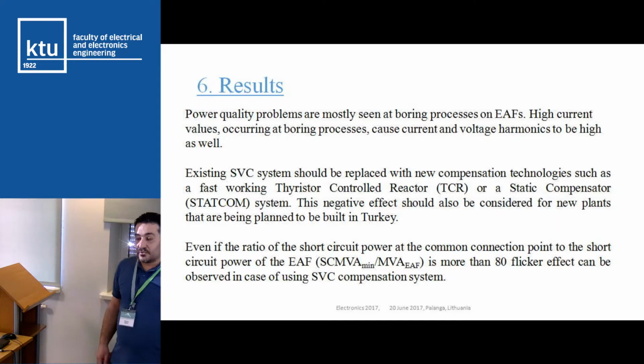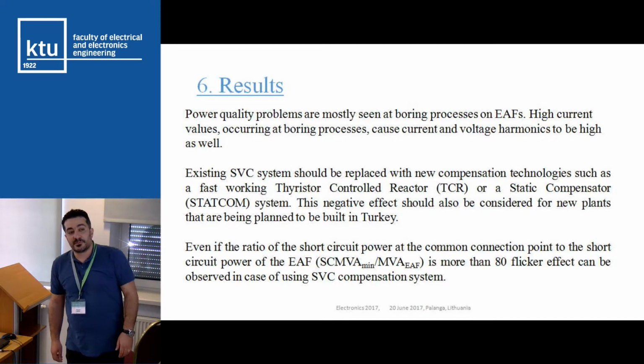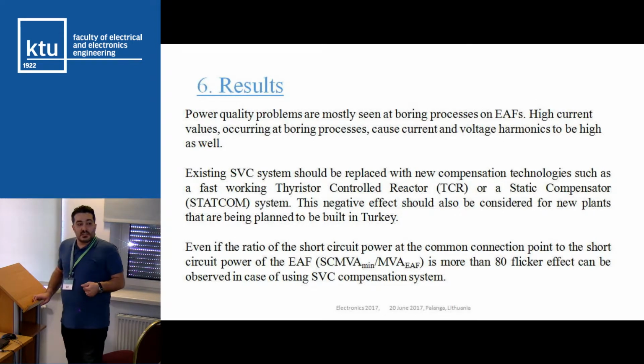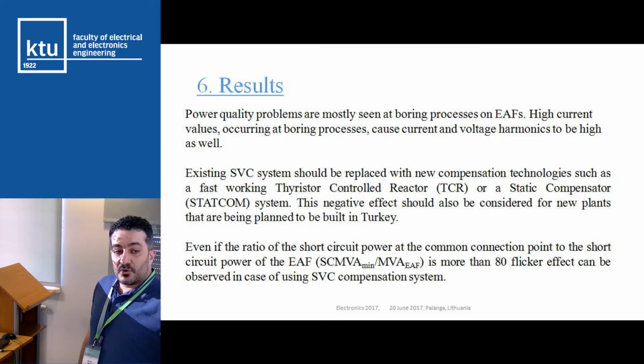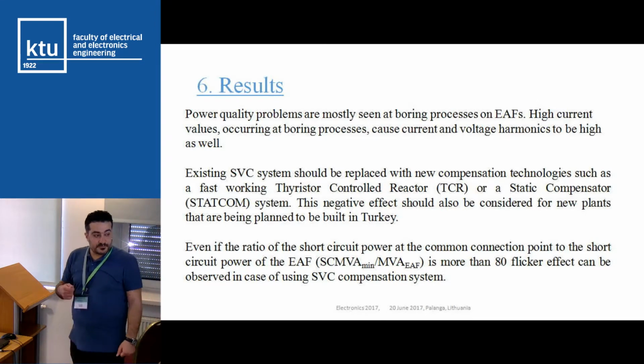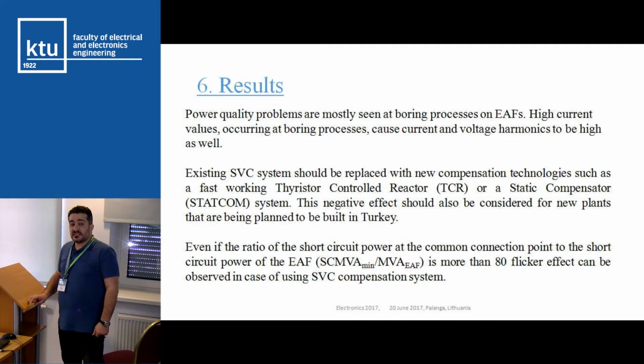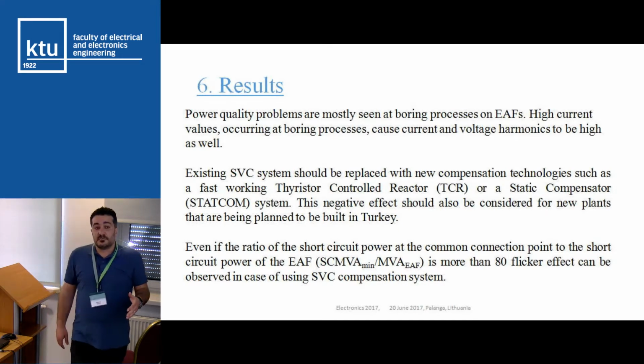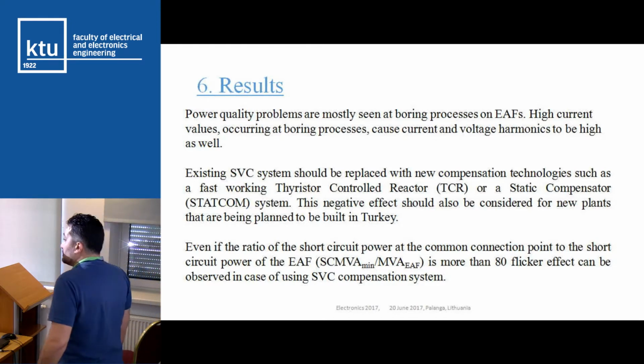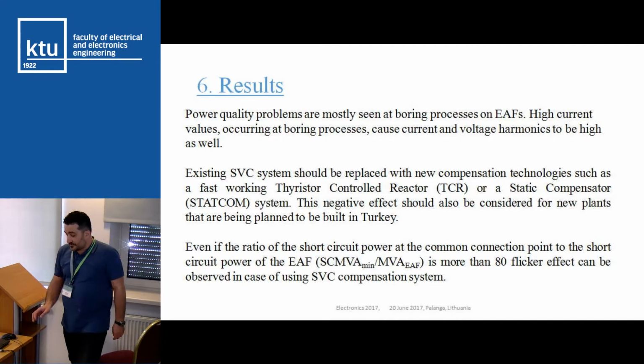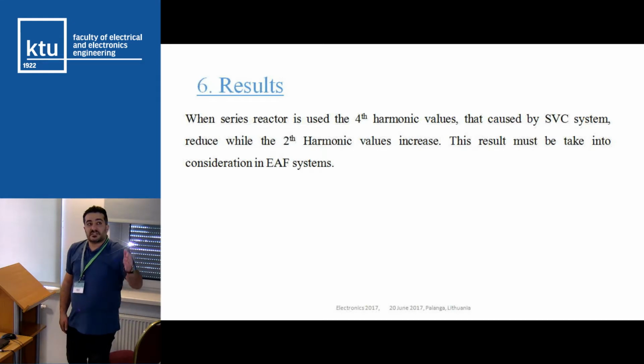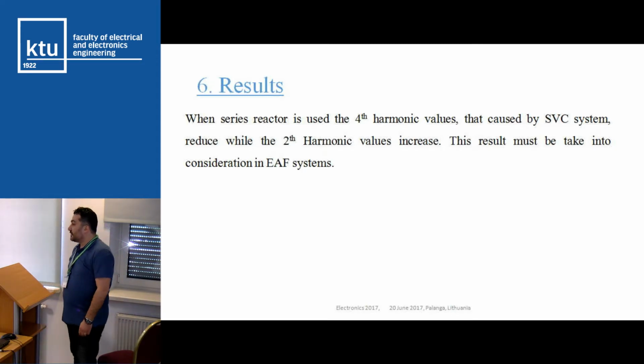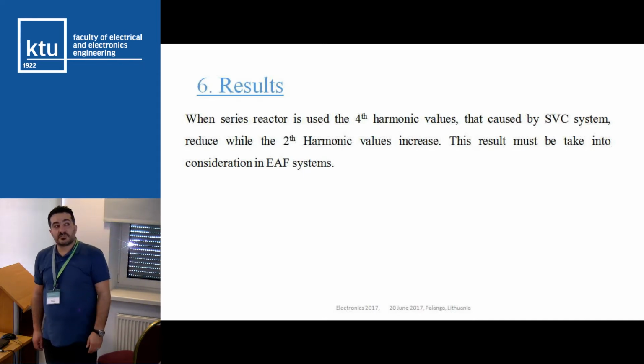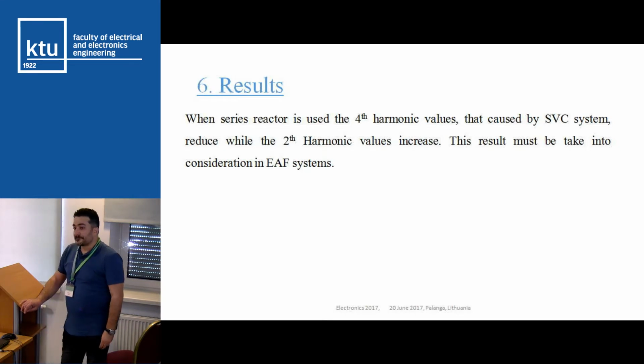And we can say that when we compare with the literature, even if the ratio of short circuit power at the common connection point is more than 80, the flicker effect can be observed, so we cannot make that assumption, because if I accept this assumption, it will not be true. We also say that second harmonic and fourth harmonic, the even harmonics, will be a problem for us, and this result must be taken into consideration for electrical arc furnaces. Thank you so much.